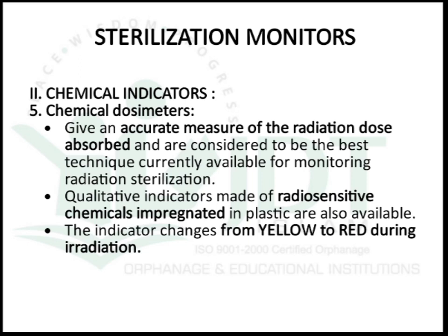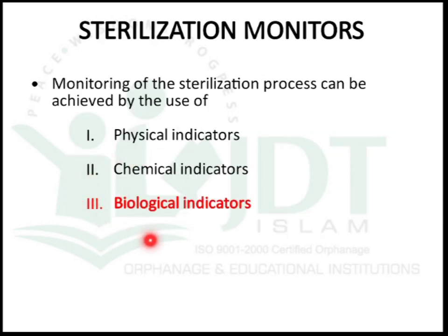Chemical dosimeters are used as chemical indicators in radiation sterilization. These substances give an accurate measure of radiation dose absorbed and are considered one of the best techniques currently available for monitoring radiation sterilization. Qualitative indicators made of radiosensitive chemicals impregnated in plastic are also available, and the indicator changes color from yellow to red during radiation.